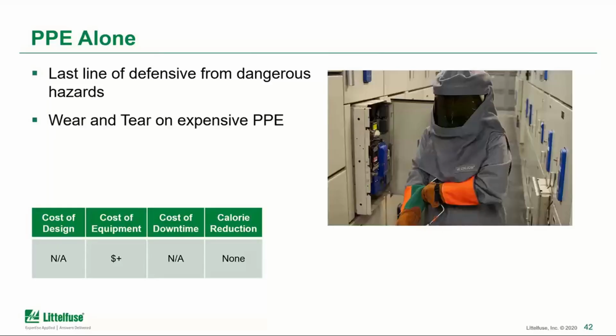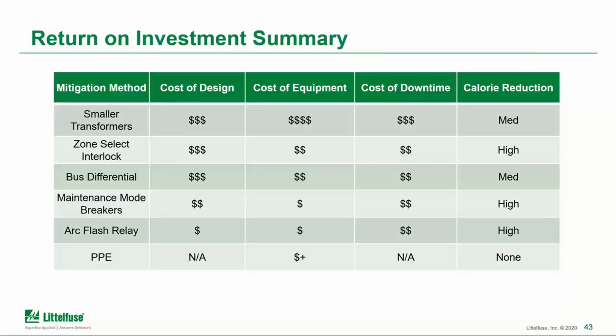And as it's shown here, there is no calorie reduction, as it's not reducing the energy. It's instead providing you with your last line of defense when you're working on the equipment if something were to go wrong. So showing a little bit of a summary here, a lot of the methods are pretty effective in providing calorie reduction or incident energy reduction, but some of them may end up incurring a little more cost of design or have a little bit higher price point on the equipment itself.